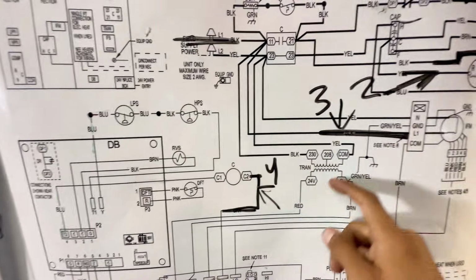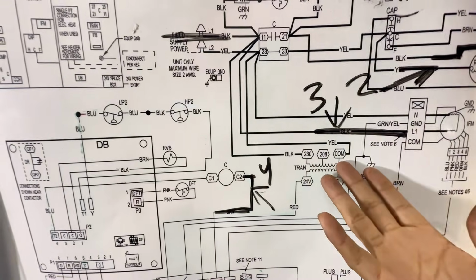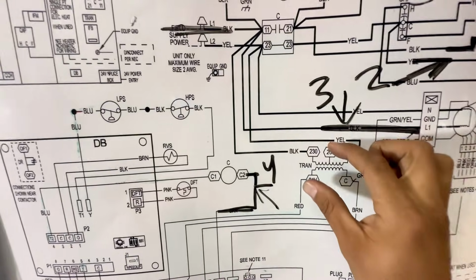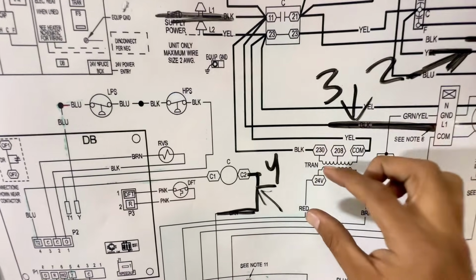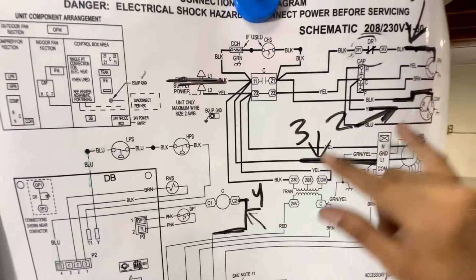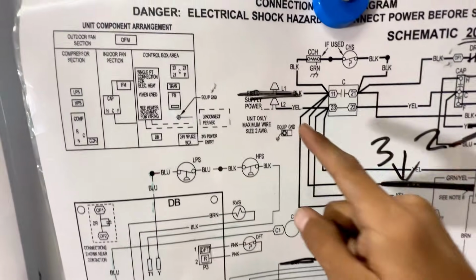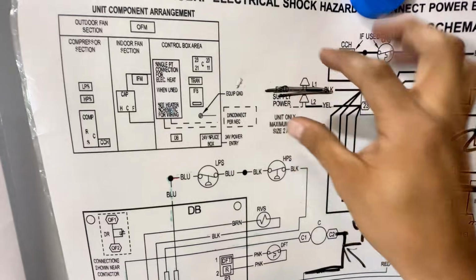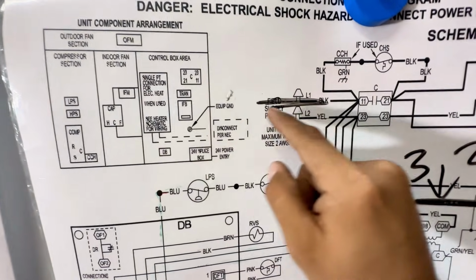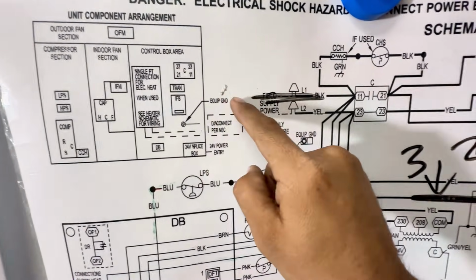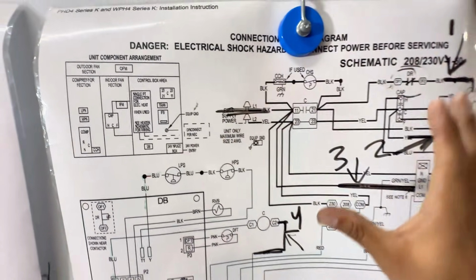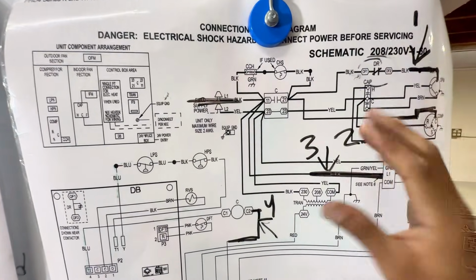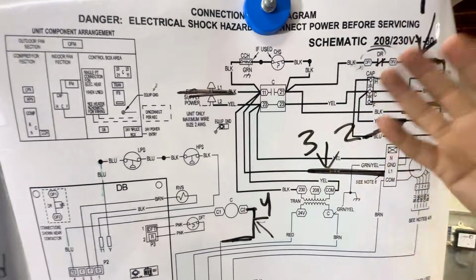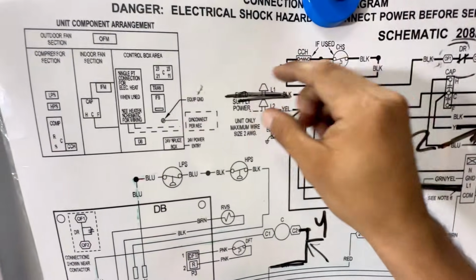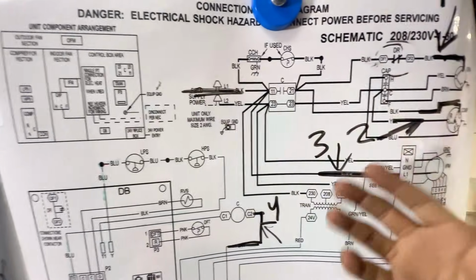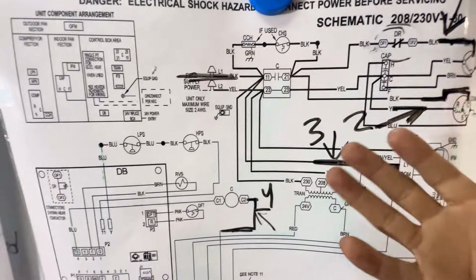We can even check the transformer too, right? Because the transformer is a load as well, right? We're going from high voltage, 208, to 24 volts. That's a load. But we'll keep it to these four for today. And I'll show you a little tip as to what you can do by checking the leg or the line coming from power from the disconnect. And by checking one, it kind of adds up all the components' currents that are on, and you're able to check it by just checking one of these legs. So that's a nice way of doing it instead of going to each one and adding them up.